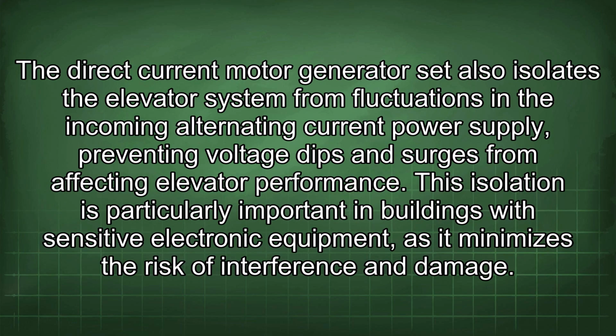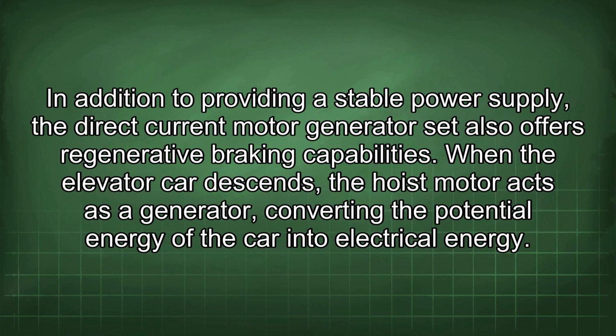The direct current motor generator set also isolates the elevator system from fluctuations in the incoming alternating current power supply, preventing voltage dips and surges from affecting elevator performance. This isolation is particularly important in buildings with sensitive electronic equipment, as it minimizes the risk of interference and damage. In addition to providing a stable power supply, the direct current motor generator set also offers regenerative braking capabilities.